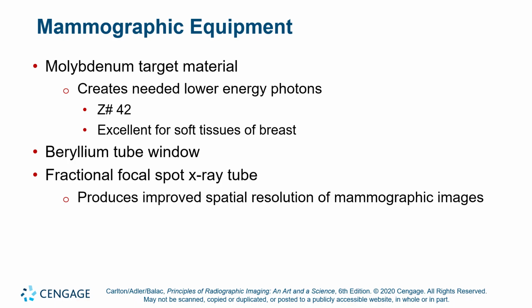Okay, fractional focal spot tube. The focal spots, the filament sizes for mammography, are even smaller than the filament sizes for general X-ray. And that's because we want high spatial resolution so we can see really, really tiny lucencies or findings, right? So we want to spot breast cancer tumors when they're very, very small. So we need a higher spatial resolution. That means we need a smaller focal spot size in our mammographic X-ray tube.